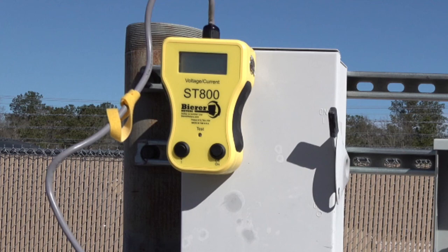Let's begin by noticing how small, lightweight, and compact the ST800 is. It's also equipped with a magnetic back that will attach to ferrous material. If the surface you're working on is not ferrous, the unit can be easily handheld while in operation. Depending on the manufacturer, there are either two switches or two push buttons located on the front of the device. The one on the right is your on-off switch or push button, and the one on the left is your V or I for voltage or current.